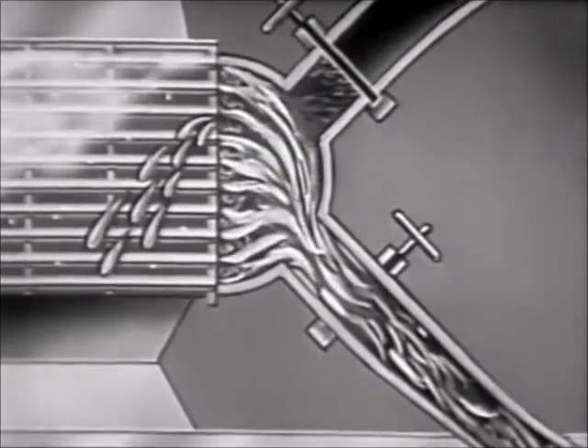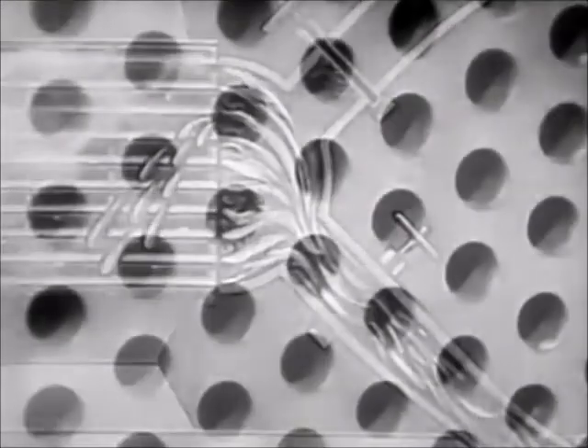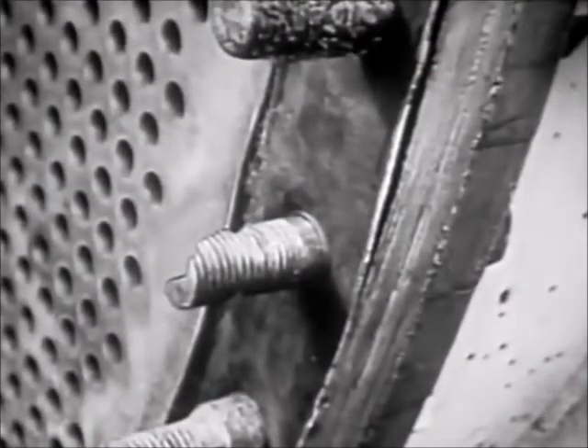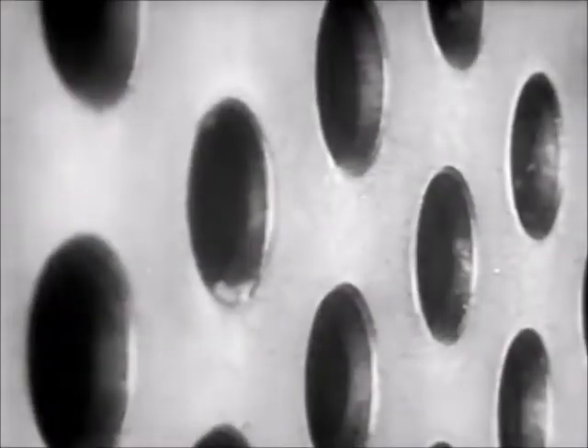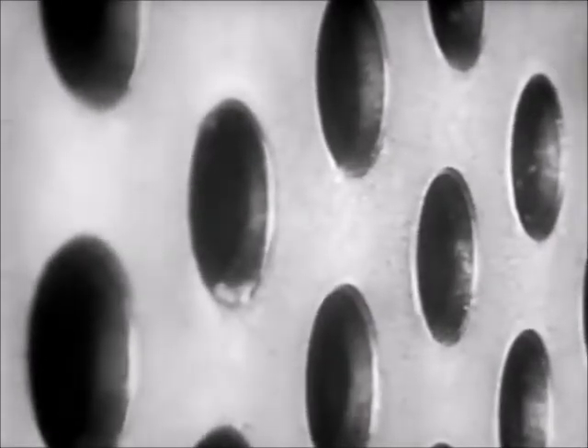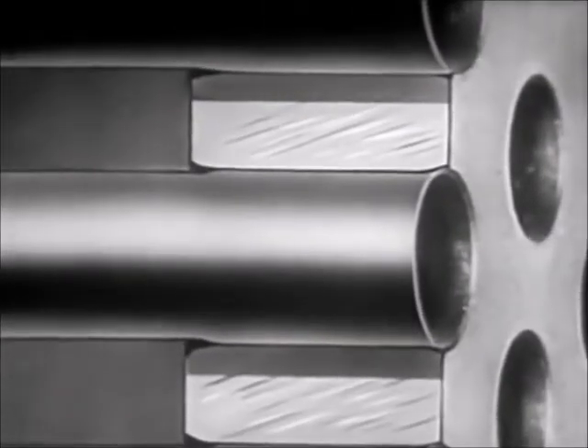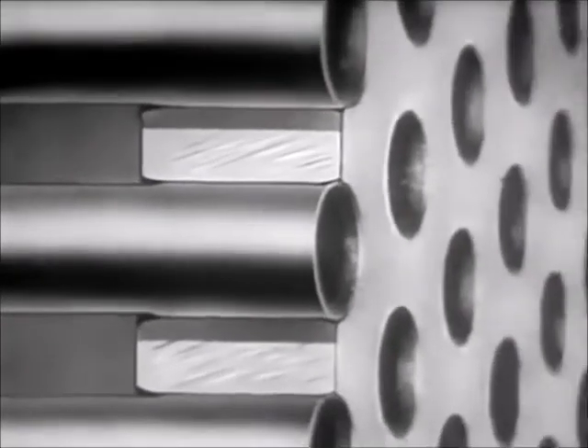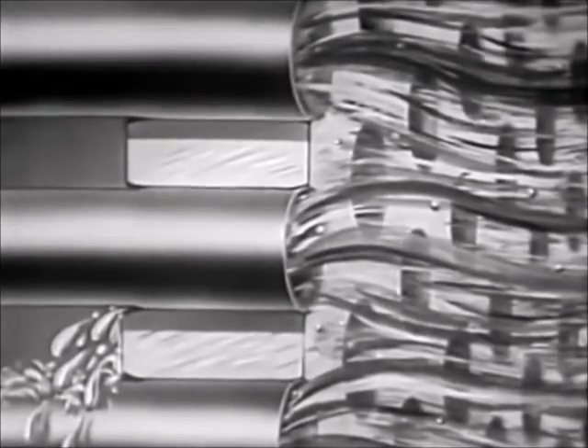Condensate is contaminated when leaks let seawater into the steam side. Such leaks may occur in the tube sheet, as cracks, as broken or corroded studs, or as leaky stay-bolt packings. Seawater leaks may also occur in defective expanded joints between tubes and tube sheets. In these joints, tube ends are expanded to make a tight fit in the tube sheet. If a tube is not expanded enough, or if a tube sheet hole is imperfect or dirty, then seawater leaks past the tube and into the steam side.